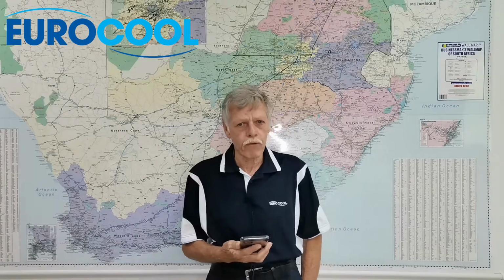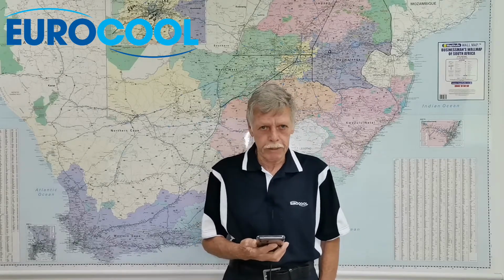E6 error code. Most common, most popular, comes up most. The E6 error code is telling you that the indoor unit is not talking to, or getting information from, the outdoor unit. Very simple. On some of the Gree units, you've got a 1 and a 2 terminal separate to your power input terminal. Don't put power on those 1 and 2. On the evaporator, on the U-Match series, you'll find 1, 2, H1, H2.